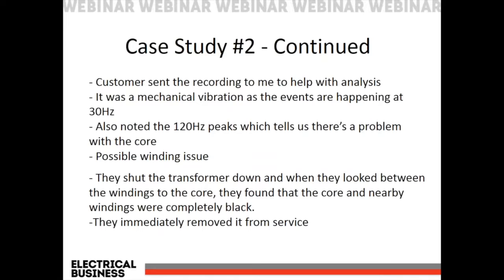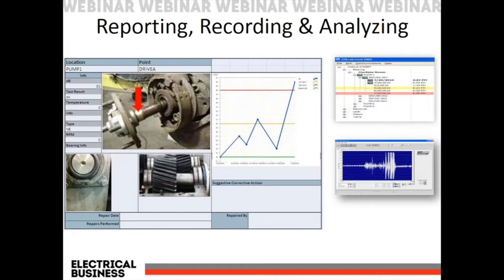Just to make a long story short here, they were able to shut the transformer down when they looked between the windings to the core. They found that the core and the nearby windings were completely black, and they immediately removed it from service. So they were able to again be preventive, through this condition-based monitoring inspection with ultrasound, right?